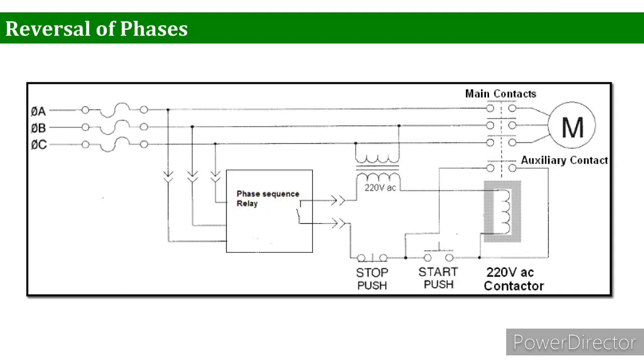from the figure, you have a motor, basically a three phase motor, and you have a phase sequence relay installed on the three phases. Whenever there is a problem of reversal of phases, the phase sequence relay will trip and stop the motor immediately, because the consequence is that the motor will rotate in reverse, and any process you are operating will get disturbed.